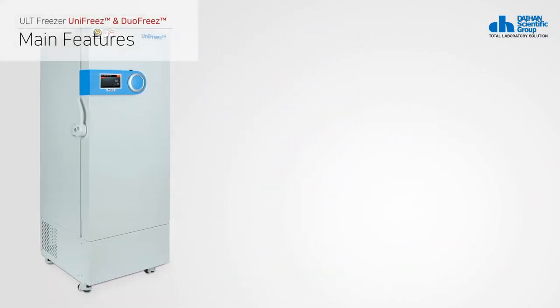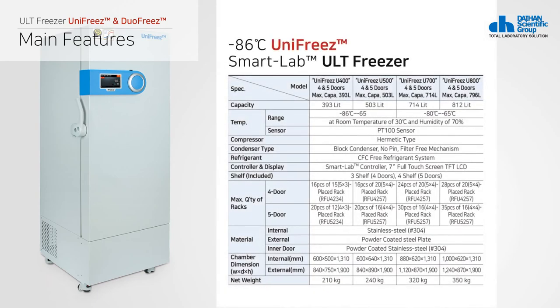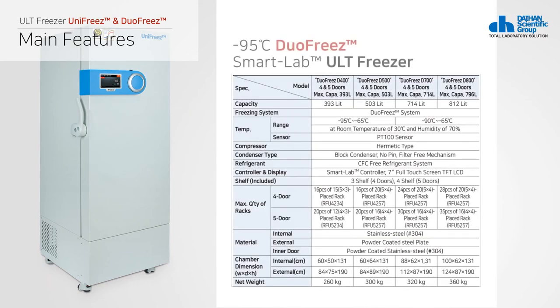The ULT Freezer uses independent dual freeze systems to ensure that the cooling temperature is maintained even if a problem occurs in one system. The ULT Freezer consists of 400, 500, 700, and 800 series. The 400 and 500 series can be used from minus 95 to minus 65 degrees Celsius. The dual freeze D700 and D800 series can be used from minus 90 to minus 65 degrees Celsius.